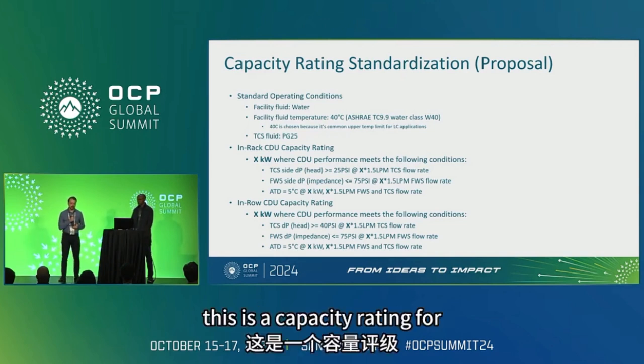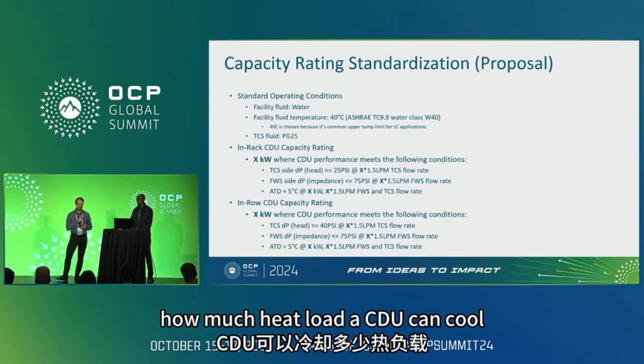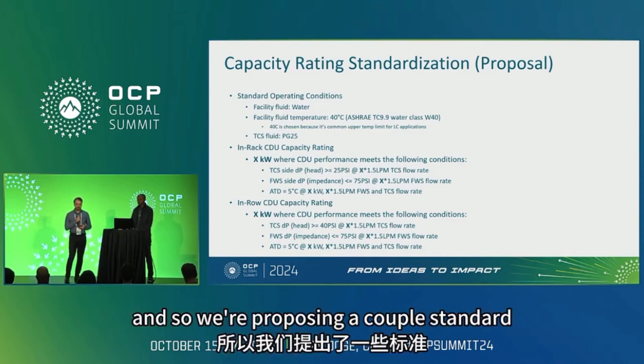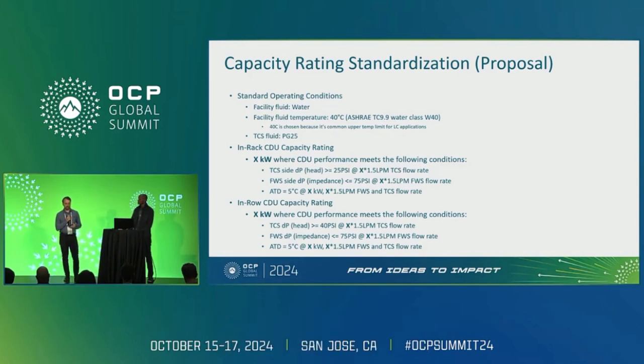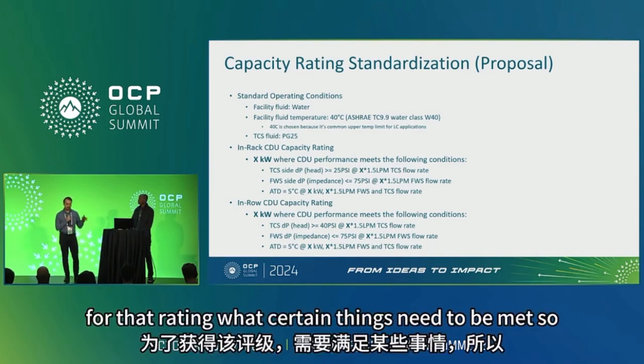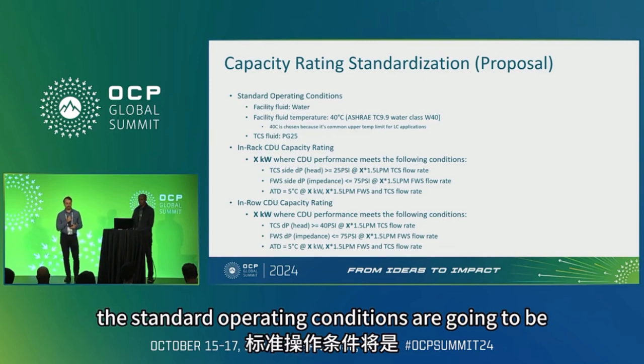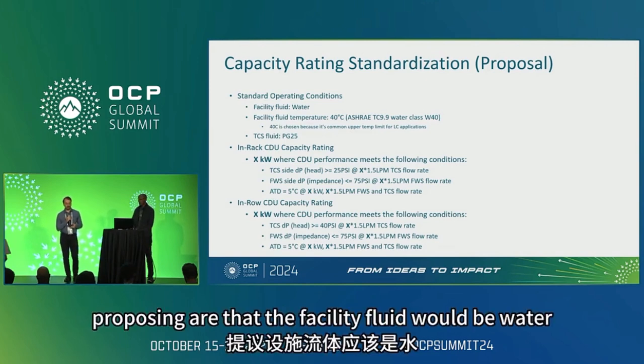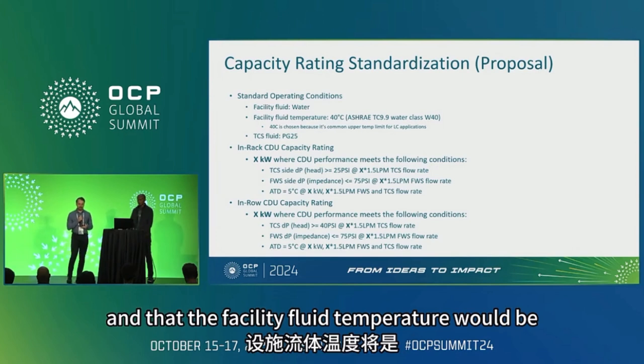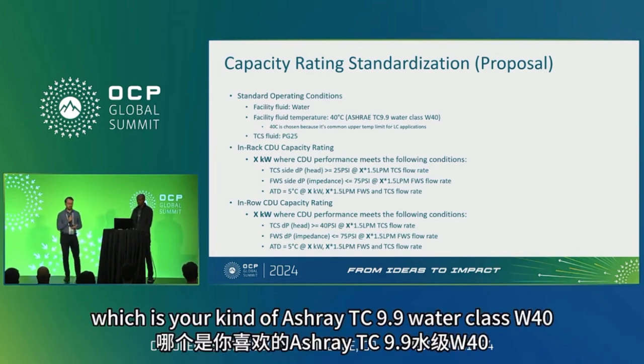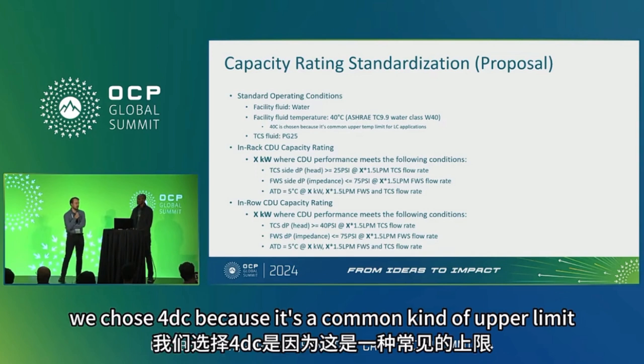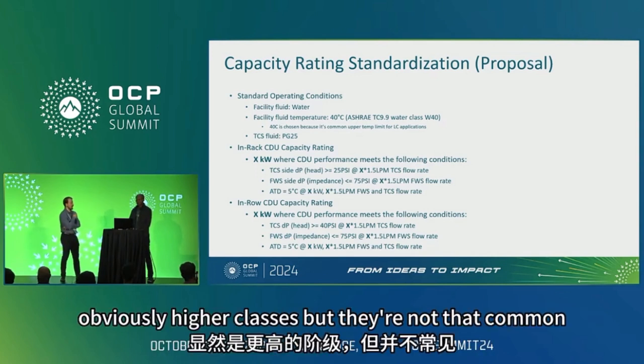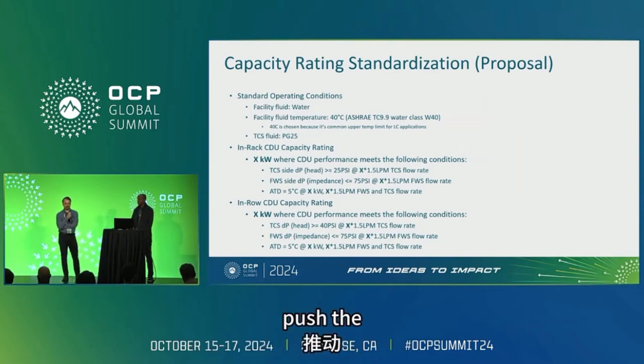This is a capacity rating for how much heat load a CDU can cool. And so we're proposing a couple standard operating conditions, and then understanding for that rating what certain things need to be met. So the standard operating conditions we're proposing are that the facility fluid would be water, and that the facility fluid temperature would be 40 degrees C, which is your kind of ASHRAE TC 9.9 water class W40. We chose 40 C because it's a common kind of upper limit. There are obviously higher classes, but they're not that common. And so we're not trying to push the envelope too much on that.